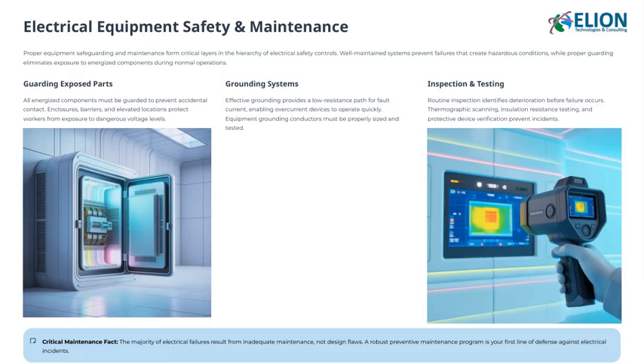dangerous voltage levels. Next, let's consider grounding systems. Effective grounding creates a low-resistance path for fault currents. This is vital because it allows overcurrent devices, like circuit breakers, to operate quickly when a fault occurs, minimizing potential damage or injury. Remember, grounding conductors need to be properly sized and tested to ensure they perform reliably.